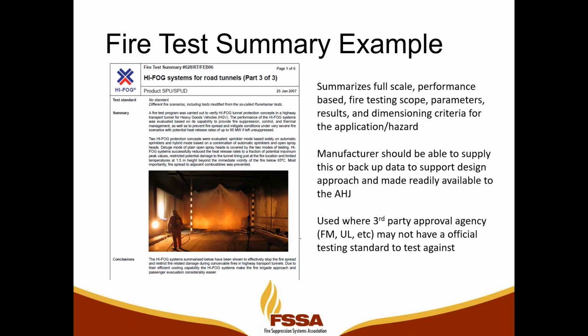When we talk about fire tests and fire test summaries, this is just an example of what a manufacturer might supply when a standard may not be available for a particular application you're looking to protect. The fire test summary on your screen is an example of testing that was done for road tunnels and their protection. That does not necessarily have an FM, a UL, or other standard that guides someone through a third-party approval. However, the fire test summary will summarize a full-scale performance-based test, and also identify the fire test scoping, the parameters, the results, and what dimensioning criteria resulted from the testing so that it can be applied to the application or the hazard.